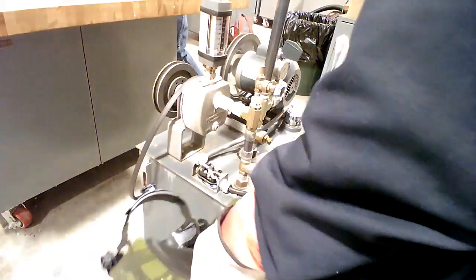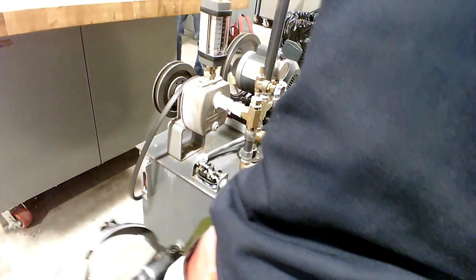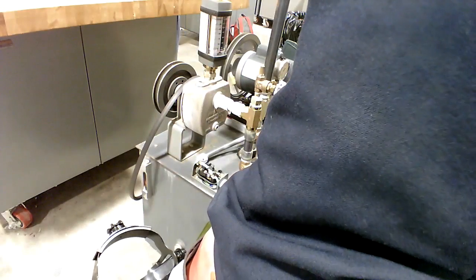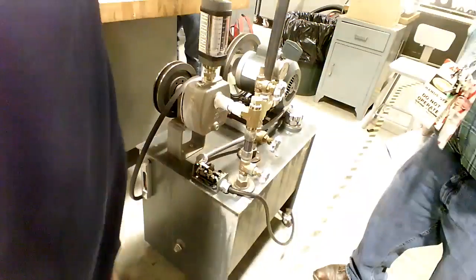That's something that has to be accounted for. You cut it off now. The overload heater in there has a time delay, so it allows for that inrush. If it stayed that high, it would trip out like a breaker. It would trip out quick. Very fast. That inrush would make it trip. If it was a regular breaker, it would trip really fast. So it has what they call a time delay to it. Now we're going to let you lock it out and then do a reversal.